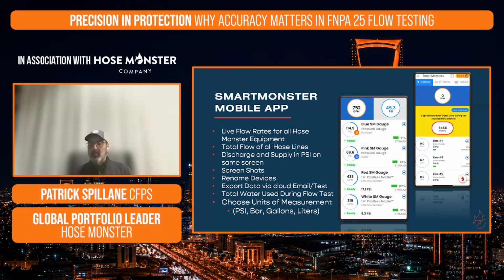So the way that device works, right? It sends a Bluetooth signal to your mobile device. It works with all iOS and Android phones. It's going to pick up that Bluetooth signal, and now your phone becomes the face of that gauge. And not only does it become the face of the gauge to show you those pressures, but it could also be adapted to our Hose Monster products to show you the actual flow rate flowing through our Hose Monster products. If you have multiple lines flowing, we can show the total sum of the water flow. And it's also going to do a live net pressure calculation of that fire pump.